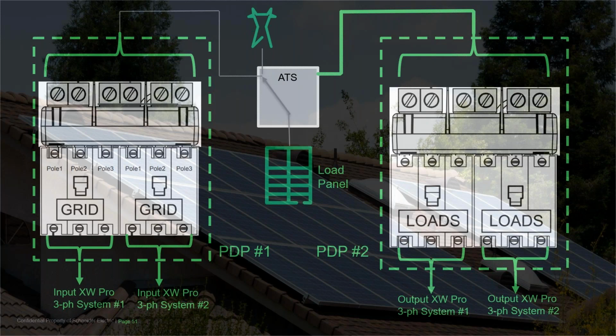For a 40 kW 3-phase system, you can still use the power distribution jumpers. You just won't be using the sliding bypass interlock plate. When using an external ATS, that already provides bypass capability. Notice during the grid-connected operation, the 6 XW Pro units will be connected on the input side and offset demand with exported power. Those two 60-amp 3-pole breakers will be combined in one of the two power distribution panels with one of the power distribution bars.